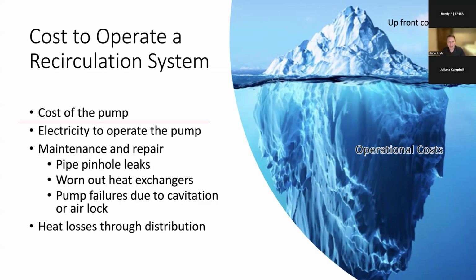So what does this mean? It means that whenever you're running the pump and you're circulating hot water through your pipes and no one's actually using hot water, your water heater has to keep turning on to make up for all of these radiant heat losses in your plumbing. So these are the main operational costs of a recirculation system. But one of these three things in particular has by far the largest operational cost. I would ask for a show of hands or pick someone from the audience, but I'm just going to go ahead and tell you what the largest operational cost is.